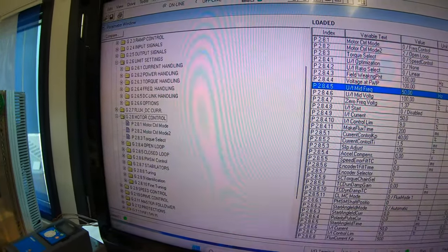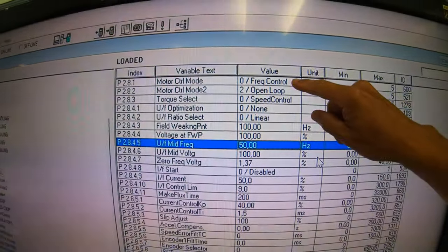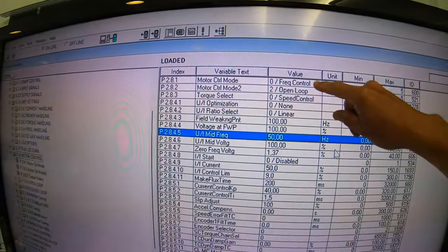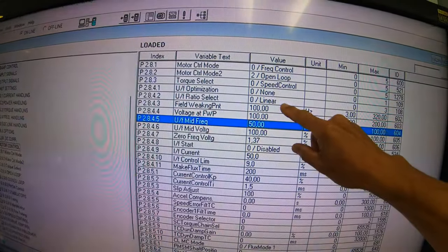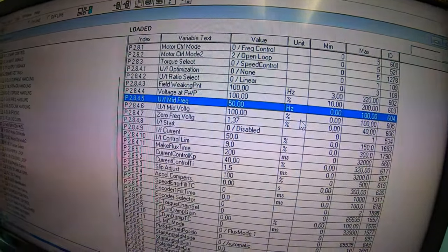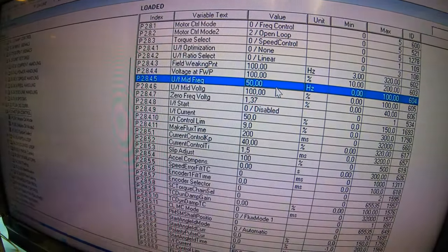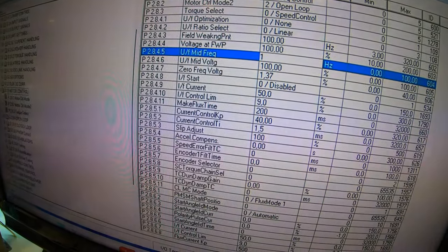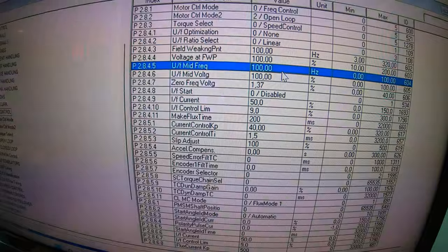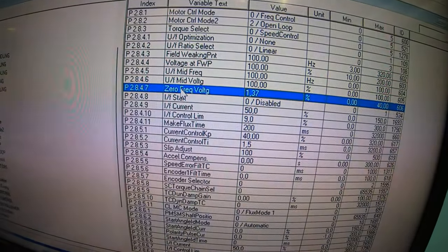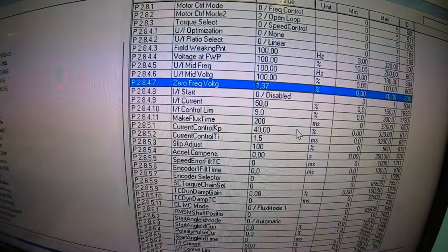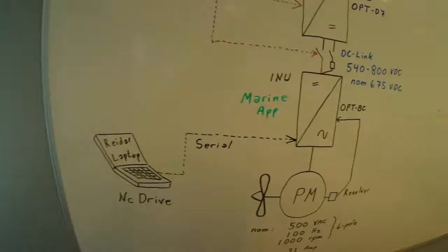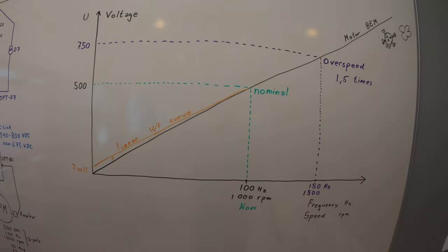Now that we got the motor parameters in, we go to the motor control, make sure that we have frequency control. We look at the UF curve and this linear curve. UF mid frequency is not 50 hertz, it is supposed to be 100 hertz, so we need to correct that one. What does this mean? It means that the driver will set out a voltage at zero frequency at 1.37% of 500 volts. That is about 7 volts.